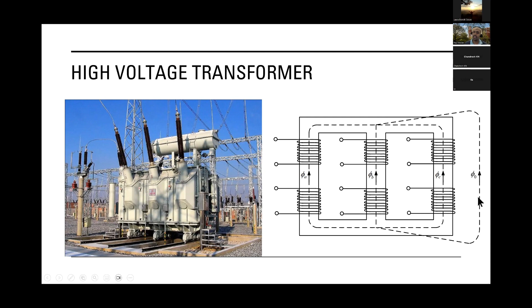And these are located at substations. Inside the transformer, you have a magnetic core and windings that are wound onto that core. And the magnetic core has a magnetic field. A transformer operates by an alternating magnetic field. From Faraday's law, an alternating magnetic field generates a voltage according to the number of turns of coil windings. So the magnetic field propagates in this core. It also comes out of the core and flows through the tank in the air. There's a component that flows there.